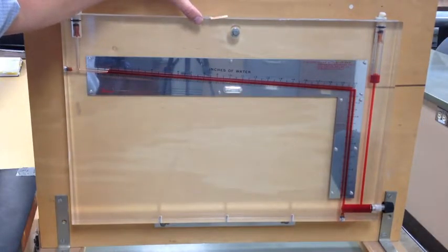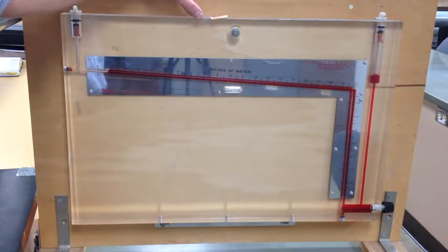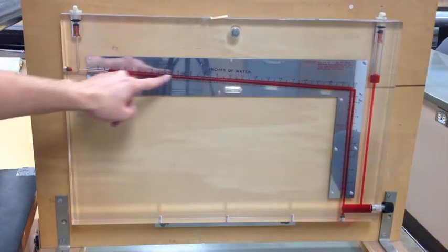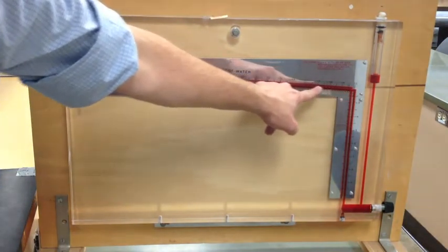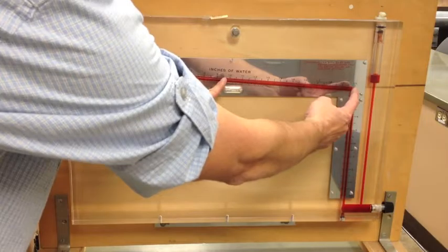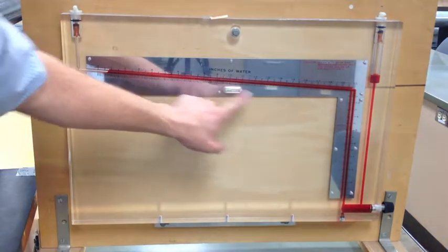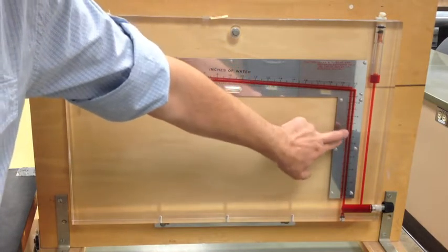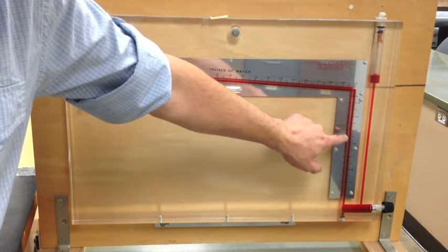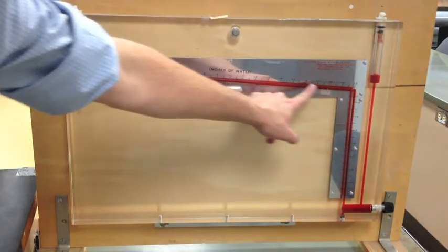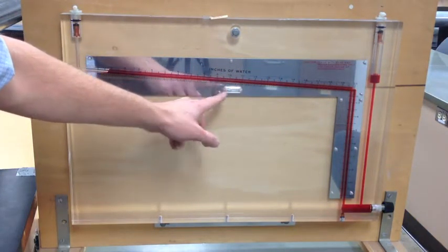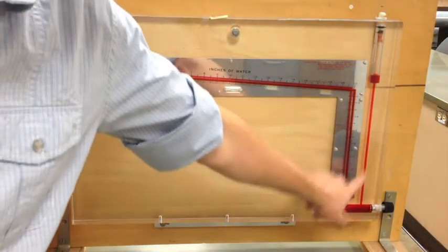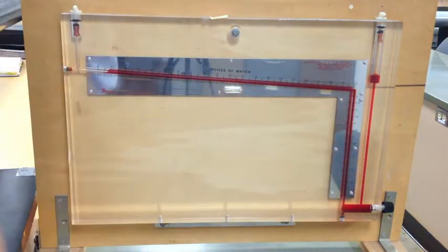Okay, here is what's called an inclined manometer. By tipping this on its side, instead of using it like that, 1 inch of water now takes up that much space. It's an easier graduation to read the units rather than trying to read them vertically where each inch and tenth of an inch is really small. Now it's spread out and much easier to read. Okay, but in essence we still have our U-tube here full of liquid.